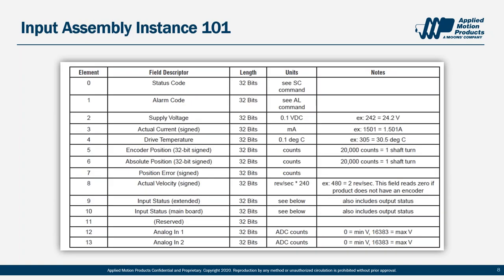The input assembly — instance 101 — contains just about everything the PLC needs to know: drive status, I/O status, position, velocity, and so on. Each of the 14 elements in the array is 32 bits long, making decoding in the PLC simple. This is the input assembly our AOIs use and it's the default in our EDS files. Instance 100 is provided only for backward compatibility with legacy applications — if you're designing something from scratch, use 101. Remember: the input assembly comes from the drive and goes to the PLC, refreshed every RPI interval.